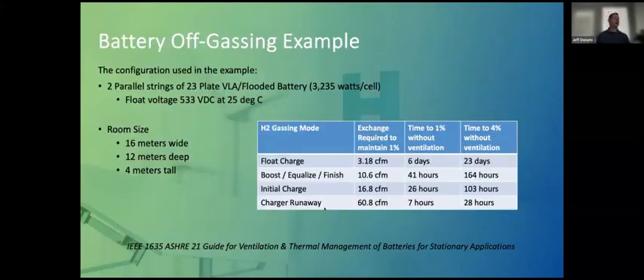So I said I was going to give you an example. This is kind of an extreme example, but it was a real example that we actually did a calculation for a specific site. This is a fairly large battery, so I'm actually giving you a data center battery as an example. But this was 2 parallel strings of 23 plate batteries, which, if you know batteries, is a fairly large battery system, but in a very small room. And we've seen these battery systems on racks that are 3 tiers high and crammed in small spaces and such. So this is kind of that example.